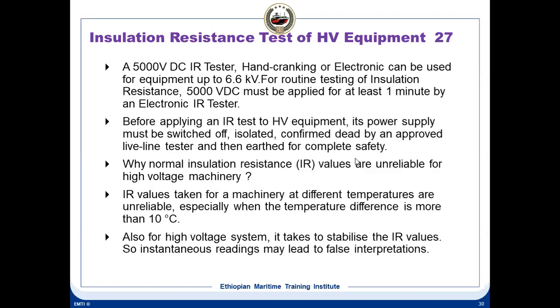That is the way it should be. It is not like normal 440 systems. The insulation testing is you have to ground it first, then you have to remove the ground before testing. Why are the normal insulation values unreliable for high voltage machineries? Because IR values taken at machinery at different temperatures are unreliable, especially when the temperature difference is more than 10 degrees. For high voltage systems, it takes time to stabilize IR values, so an instantaneous reading may lead to false interpretations. So for high voltage systems, IR values are not that reliable.